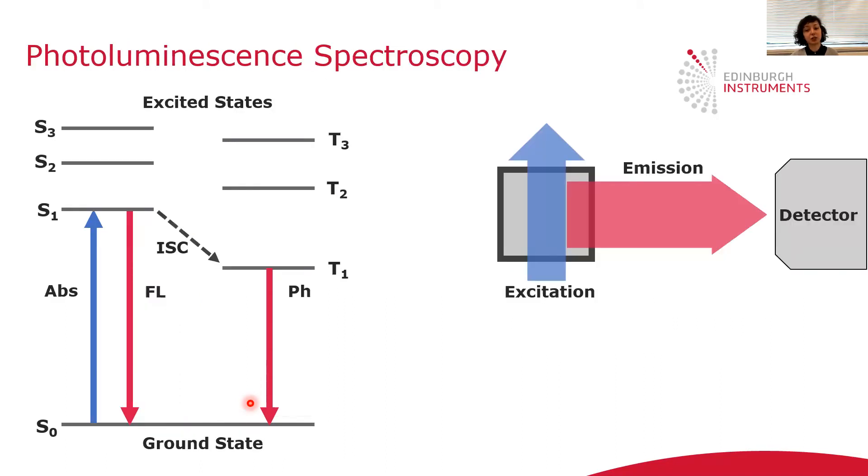As I mentioned, you will study the radiative relaxation processes by photoluminescence spectroscopy. You would use a photoluminescence spectrometer, where you have an excitation beam going through the sample. This is the sample. Then the emission is studied at the right angle to avoid interference from excitation. And the light is filtered out using a monochromator.